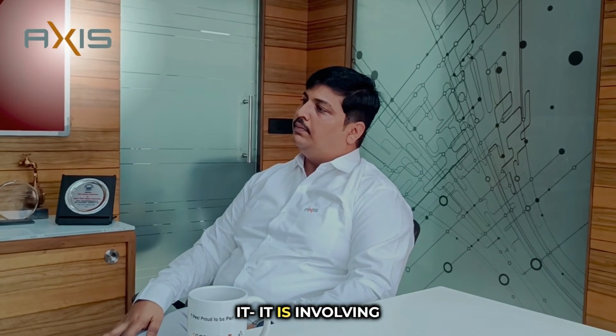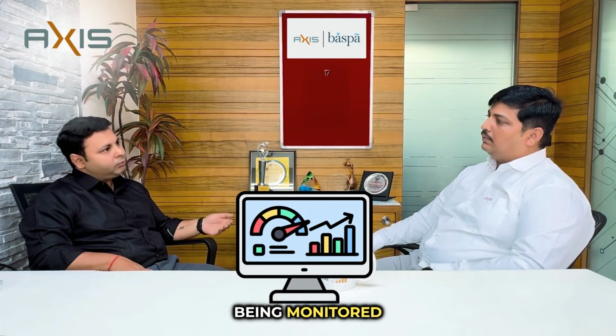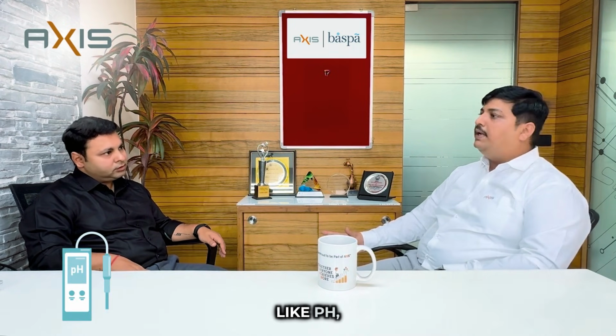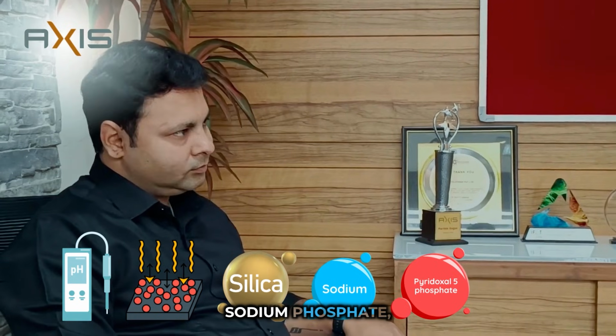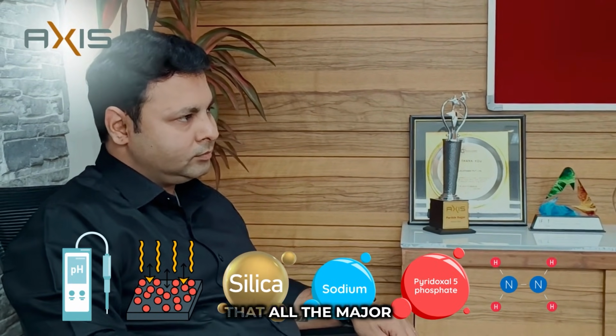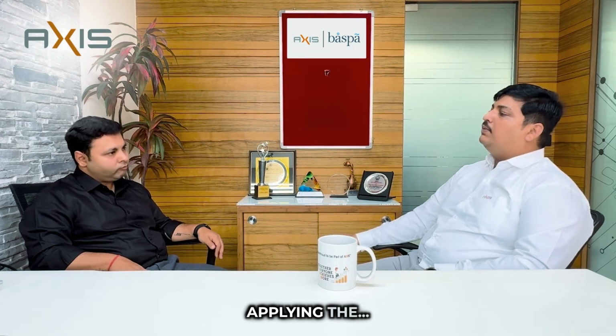So when we talk about power plants involving water, steam, turbine, boiler, the major impurities are also present in the water or steam. So what are the different typical measurements or parameters monitored by SWAS? Okay, the parameters are pH, conductivity, silica, sodium, phosphate, hydrazine, and dissolved oxygen. These are all major parameters we need to monitor before applying any steam or water to the turbine blade.